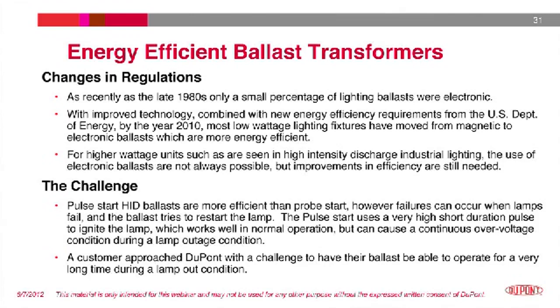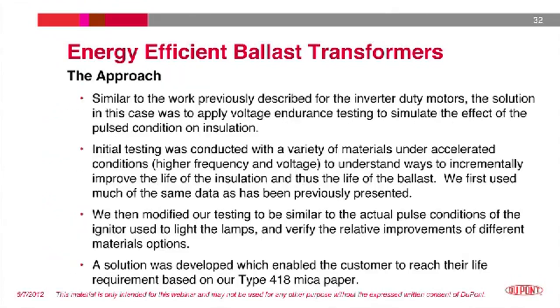The downside of this type of design happens if the lamp has failed. When a lamp fails, the ballast tries to restart the lamp, and a very high voltage pulse is then imposed on the ballast, much higher than the typical operating voltage. This overvoltage is now continuous for long periods of time rather than for very short duration. This caused a higher failure rate than seen with probe start ballasts, and one manufacturer approached DuPont with a request to help solve this problem.